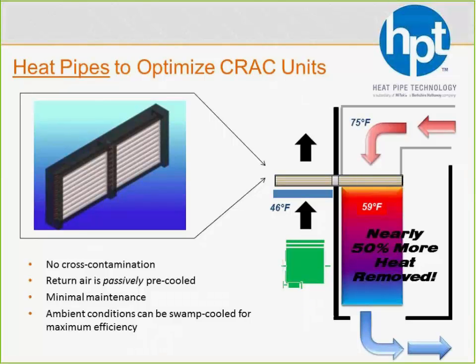It's also something you can plug into Select Plus, our software, and once you pick your location, it'll show you how cool you can actually get the air based on the wet bulb at those bins. So by being able, especially, to put an evaporative cooler on there and get even more BTUs, and do so by simply adding a little bit of static without any power, now we're not only a very effective device, but a very efficient device, especially when it comes to RER, which is always great.